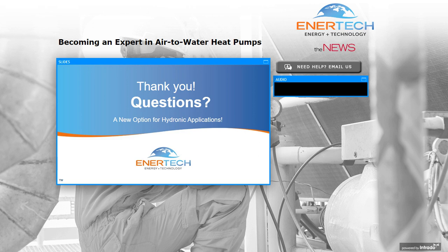Rodney, have you used this product for pool heating? I don't know if we have any applications today that we've used it with pool heating. We certainly have used a lot of water-to-water heat pumps for pool heating, and it would apply the same way, really. It would just be another hot water zone. We would have to have a titanium plate heat exchanger so that we didn't have pool water going through the unit, but it could be used for pool heating just as another heating zone.